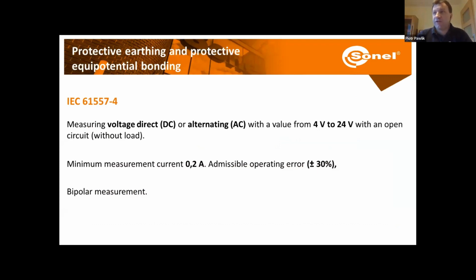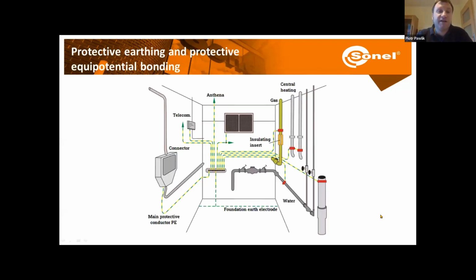Now let's look at the additional protection. So the equipotential bondings and RCD parameters. So first, equipotential bondings. Here the standard tells us to measure it with the test current of at least 200 milliamps. And the flow of the current during the measurement has to be in both directions. So, well, basically these days, all of the modern meters that allow for continuity measurement can perform it this way. And in practice, how does it look like? We're going to connect a meter with one of the test leads to the main grounding rail. And then with the other test lead, we are going to go and touch the protective contact in every socket or at every device which is connected with the PE wire. And this is in order to make sure that our PE wires, protective wires, they conduct well and that they are not broken.